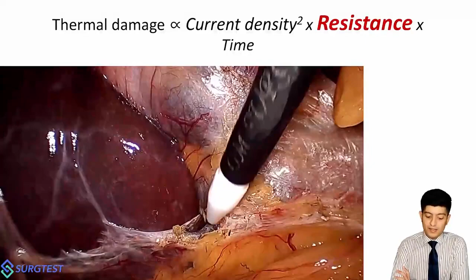The other important determinant of thermal damage to the tissues is going to be time. Now, this is a no-brainer, right? The longer amount of time you keep the pedal pressed, the more energy is going to be delivered to the tissue and the more likely the chance of iatrogenic injury. This is particularly true of the coagulating current, which is a high voltage current that has the greatest propensity to do damage to the patient's tissues. So whenever you can, use short bursts of energy, use the correct mode for the task at hand. You can't use the same current all throughout. It's just not a smart way of operating.